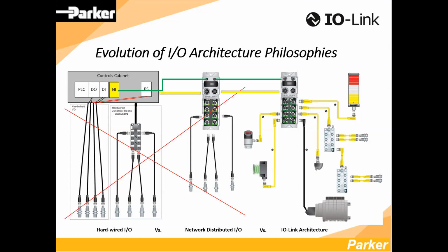The IOLink devices are going to be the same ones you've been using all along, except instead of having a discrete interface, it's going to have an IOLink interface. No more cost, and we'll get into that. Basically you're connecting that to a master, an IOLink Master module, which is the field bus module. What normally would have been connected to the field bus or just discrete wiring is now connected through the master. Think of a master as a gateway, and one definition of a gateway is a conversion between two protocols. In this case, it's whatever field bus you're utilizing and IOLink.